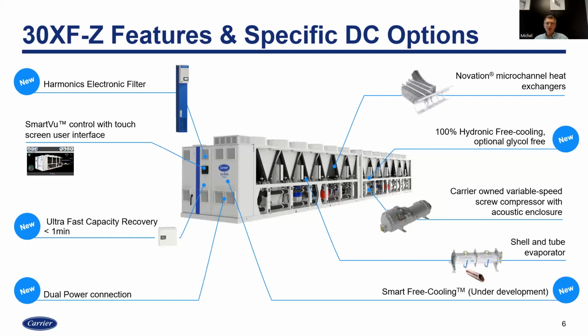We have special inserts inside the tubes, and this is a very important feature, which makes operation of our evaporator possible with very, very low flow, which means that we can go from 100% to 15, maybe 17% of capacity with constant delta T with very, very limited flow. And this is relatively unique. So it makes hydronic installation very easy. You don't need to have any recycling pump.